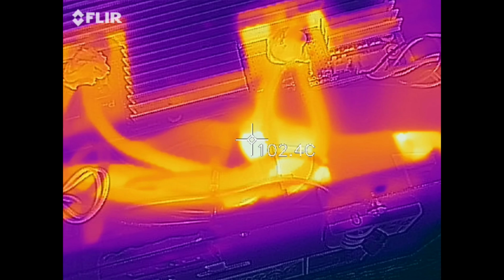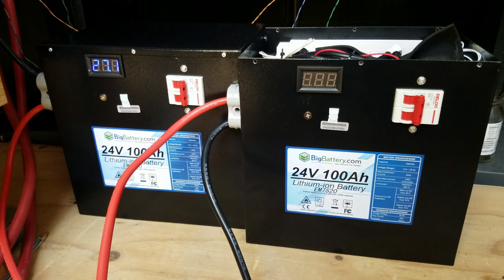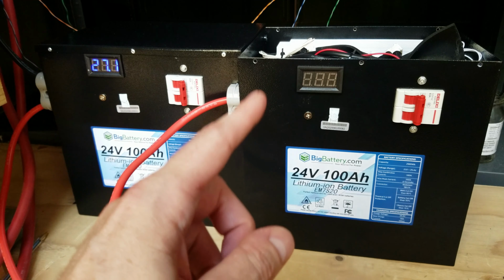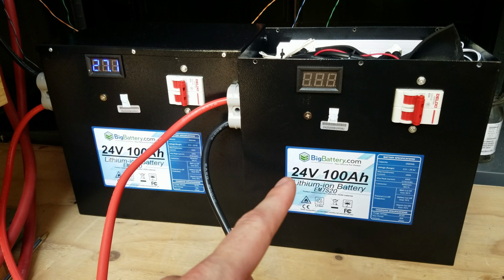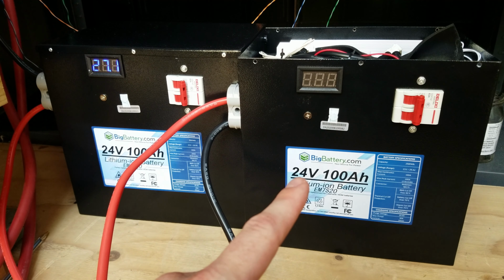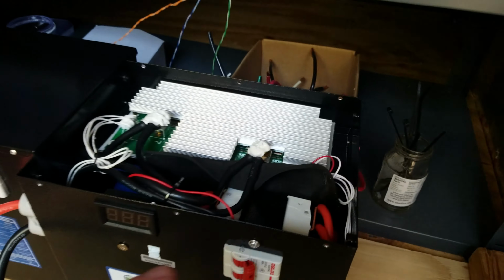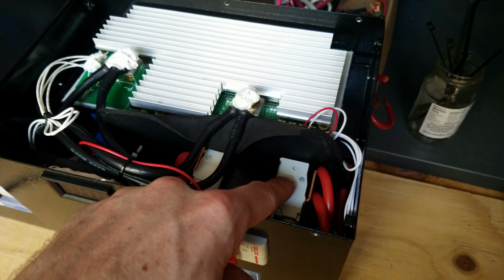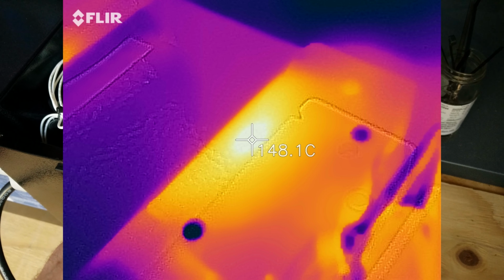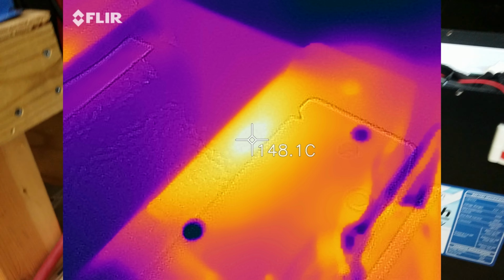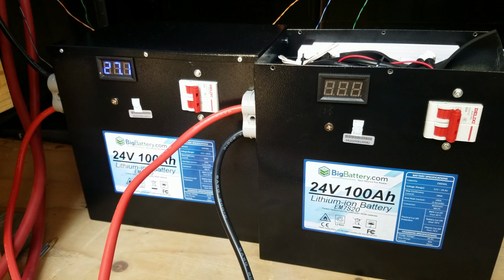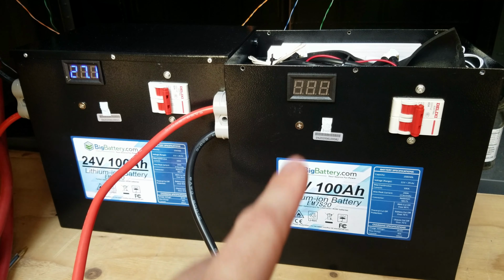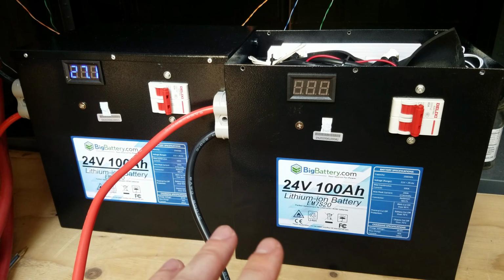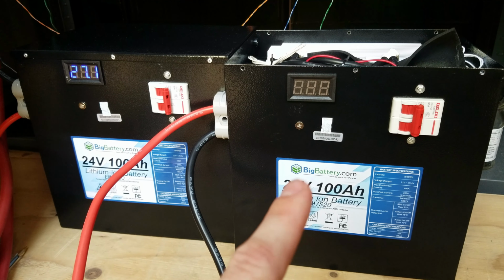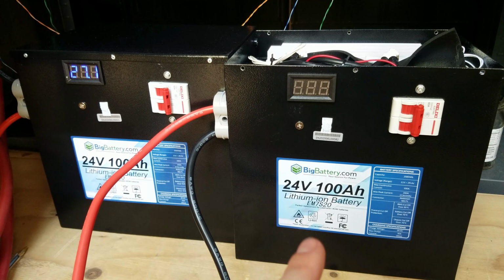I'm not really sure what that's about, but alright guys, so we got about 15 minutes into that test, and this unit on the right actually shut itself down. I had my thermal camera on the circuit breaker, the top corner up here, and I was reading 150 degrees Celsius. And then about a minute after I took that reading, I was sitting here watching it very carefully. It made this click sound, and it just completely shut off with that 100 amp load on it. I don't want to say it doesn't surprise me that it couldn't handle 100 amps, but I know I was pushing it with that kind of load.